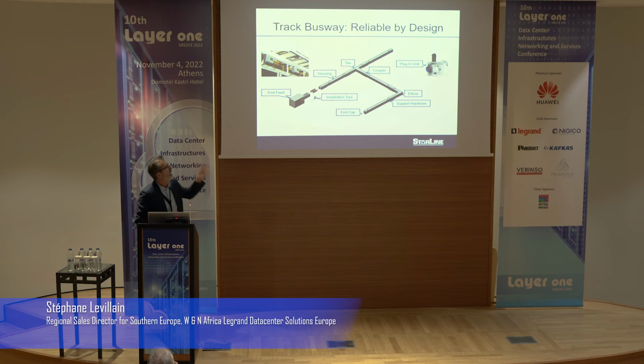End feeds are where the cables come from the UPS. Then you have the straights, which are the bars, open channel bars. You have end caps, and you have plug-in units, the tap-offs that you insert to feed the rack. And you have a very important piece, I would say it's a key piece: the joint kit. The joint kit is the small piece with the copper blades, and this is the key brick to give reliability to your installation, to your solution.